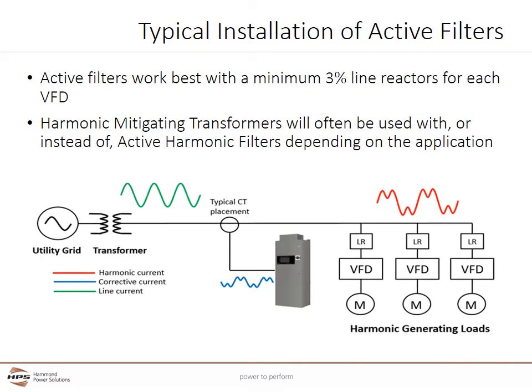Active harmonic filters work best with a minimum 3% line reactor or DC link choke for each VFD. Line reactors help lower the total harmonic current, which also aids in being able to size a lower current-rated and less expensive active harmonic filter. Harmonic mitigating transformers phase-shift harmonic currents, which can also cause harmonic current cancellation, and are most often used to cancel harmonic currents caused by single-phase harmonic sources. Multi-pulse transformers are also often used with medium-voltage drives for current harmonic mitigation. 18-pulse transformer technology is still sometimes used with low-voltage VFDs but is largely being replaced with active harmonic filters.